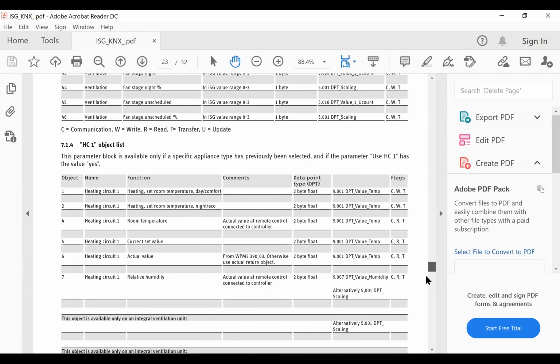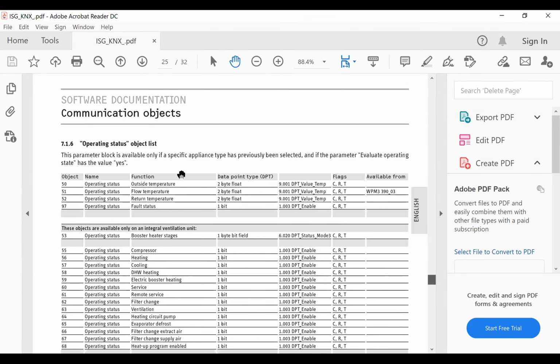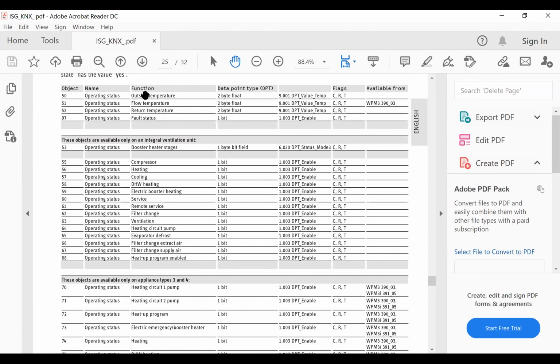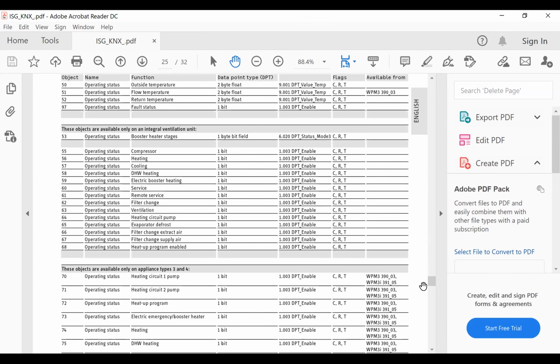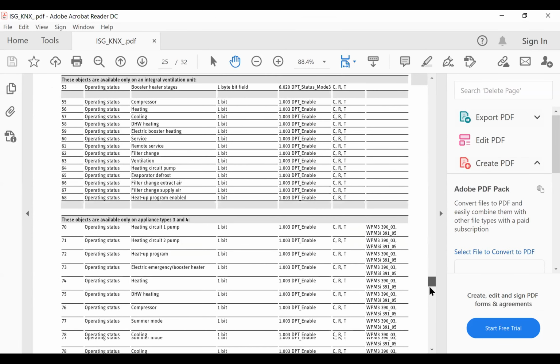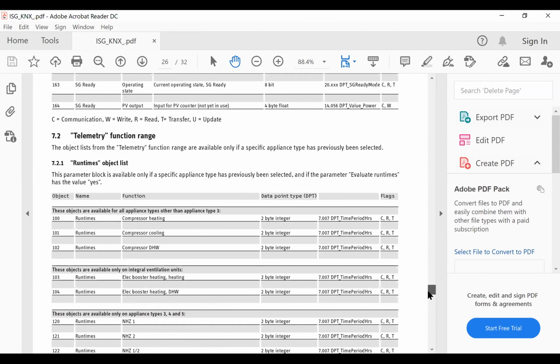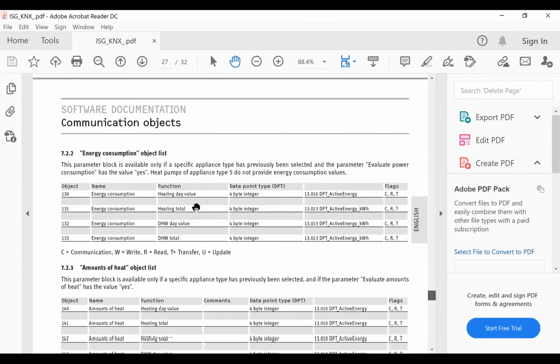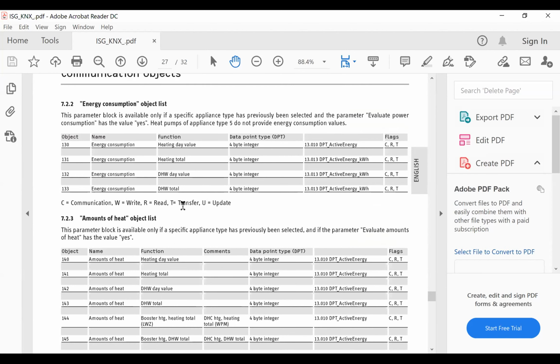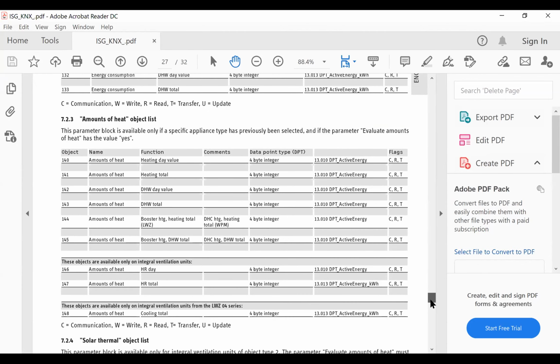There's read and there's write points, but you can see all this. You can see what the operating status is. I want to know what the flow temperature, the return temperature is. You can bring all this into your BMS, and that BMS can then use that data. If it's sophisticated enough from a heating and cooling point of view, it can use that data to turn on and off circuits and control temperatures. So this is what we would consider the high-level control, where you've actually got a network-controlled BMS, be it Modbus or be it KNX, going in and taking control of our system through our ISG.